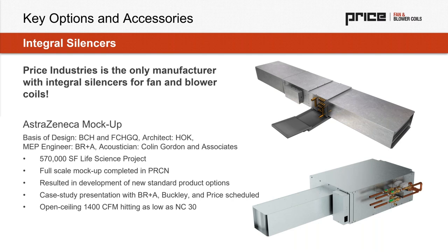Anecdotally, I've had a project that I worked on where there were duct attenuators close coupled to equipment, and they actually created kazoos instead of silencers. That's because these duct silencers are heavily baffled, more heavy duty built pieces of equipment, and the reality is they actually generate noise. They have an insertion loss. They take out more noise than they generate. But the truth of the matter is they're tested with 5 equivalent duct diameters, which we almost never see on projects. My general rule of thumb recommendation is to have at least 2 feet upstream, or 2 duct diameters if you can get it, which is really nice. But generally we don't see that. And if we're close coupling that to a fan, it can be very problematic.